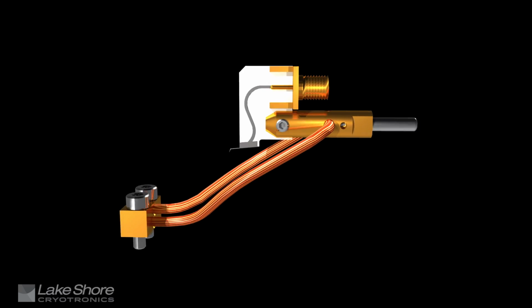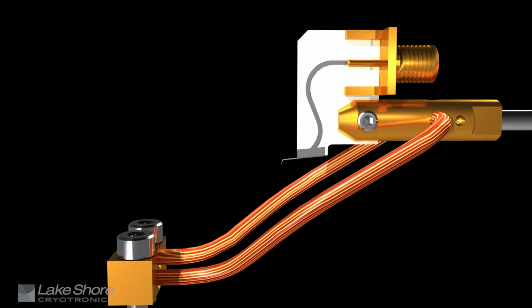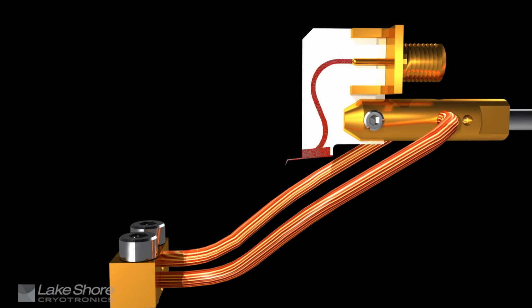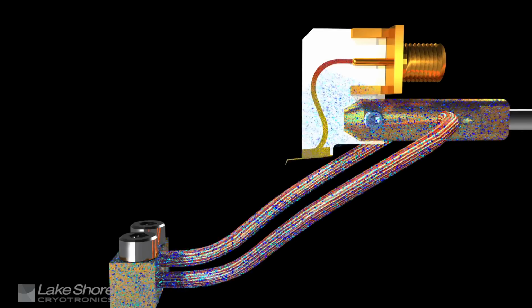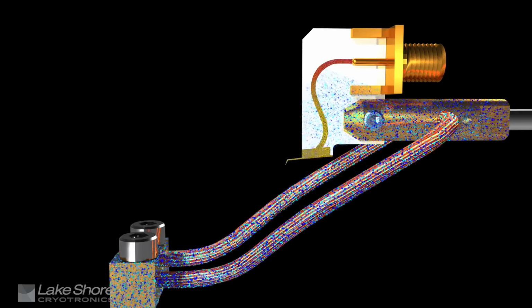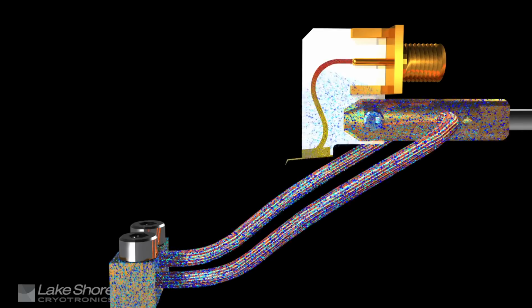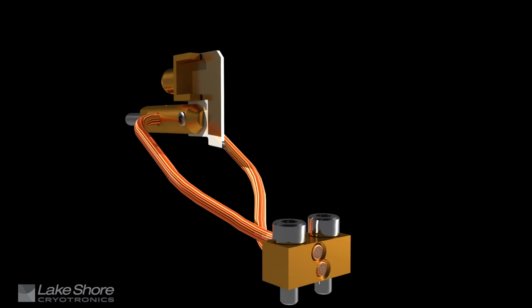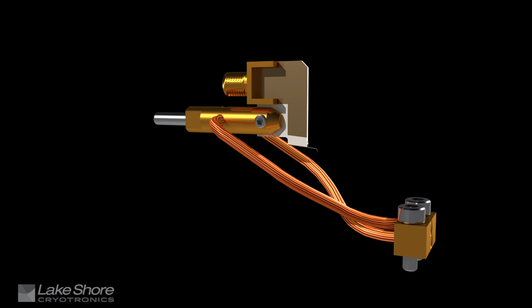A Lake Shore ZN50R DC probe is different in that it is designed in a way that transitions the signal from the signal cable to a temperature-stable ceramic blade that is cooled by the probe mount prior to transitioning to the probe tip. For general purpose DC measurements, the backside of the ZN50 blade is grounded, and for high impedance DC measurements that require a guard voltage, the backside of the ZN50 blade is driven by the guard voltage.